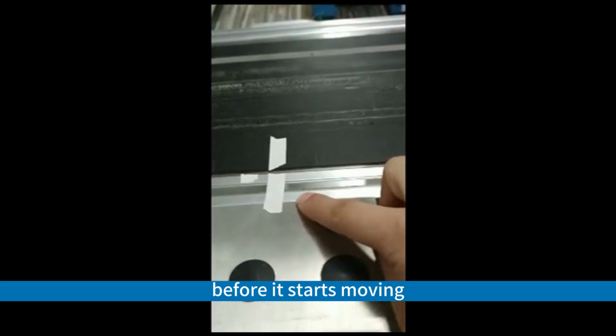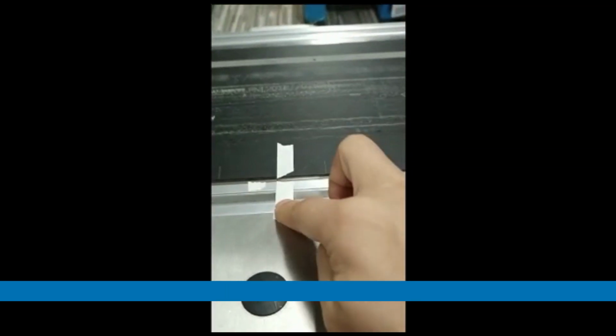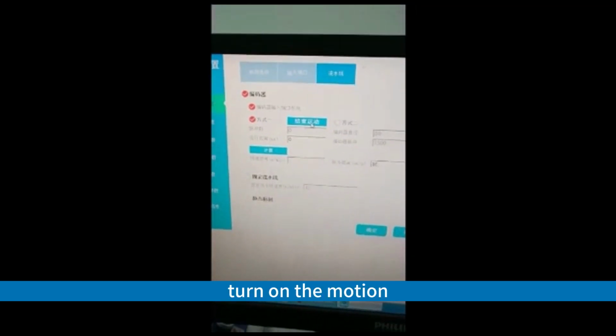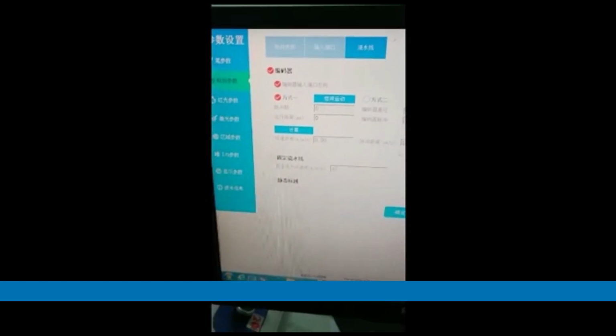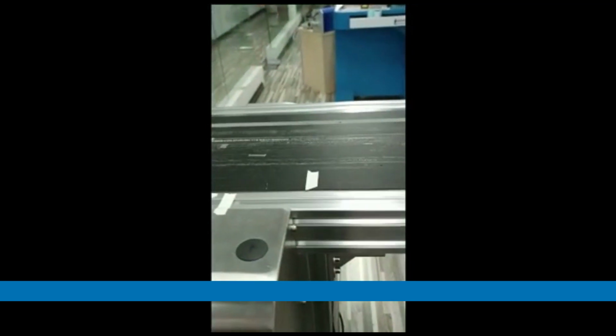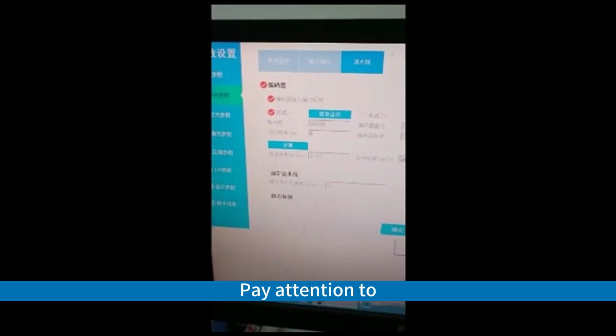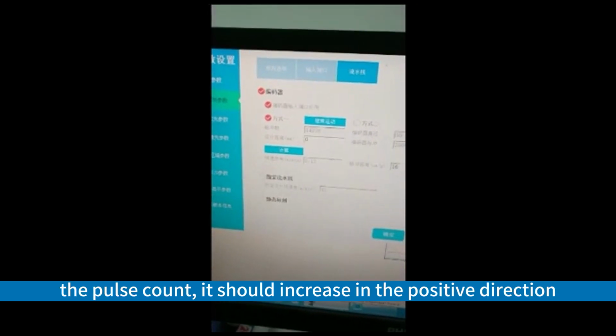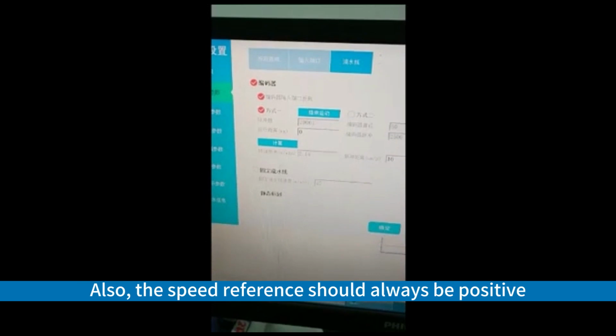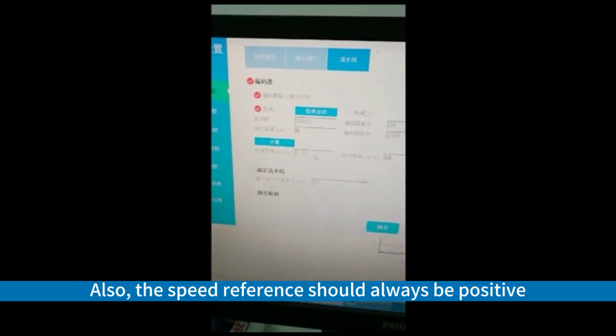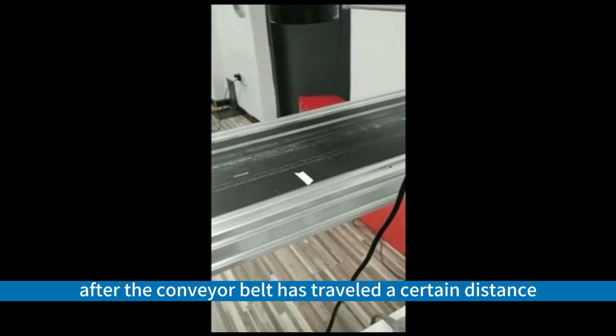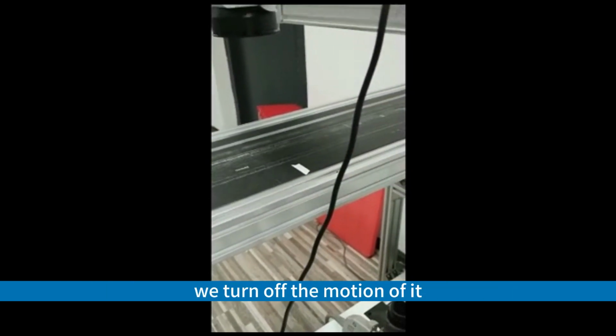before it starts moving. Then, turn on the motion, and it starts moving. Pay attention to the pulse count. It should increase in the positive direction. Also, the speed reference should always be positive.